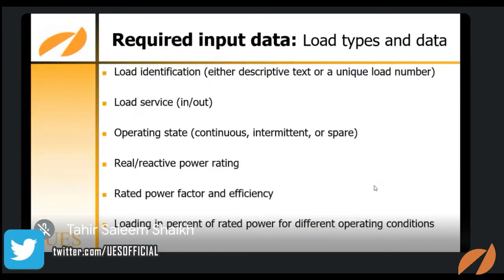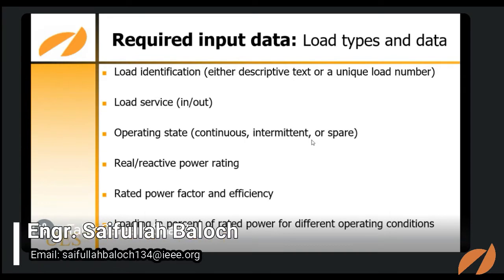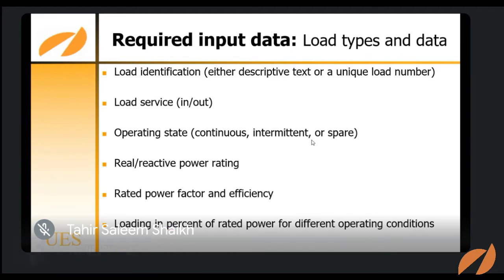Now these are things you have to put in that software, or if you are doing a manual calculation: the load identification, what kind of load you are using, whether the load is in service or out of service, and the operating condition. You have to be careful whether it is continuous, intermittent, or spare. Real power and reactive power, because whenever you are purchasing something from the market, you can see a nameplate having such data. Rated power factor and efficiency, what is the rated one?